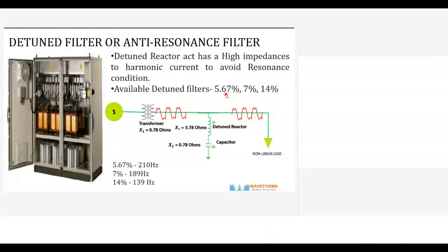Basically, these are not harmonic filters. The myth is that some people believe this will mitigate the harmonics. It will not mitigate the harmonics. It just blocks the harmonics and prevents the resonance. Whatever harmonics are there in the system will remain. It will only stop the amplification or magnification of the harmonics. That's all. I'm trying to dispel that myth.